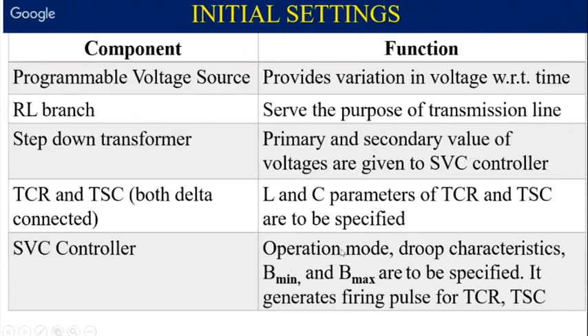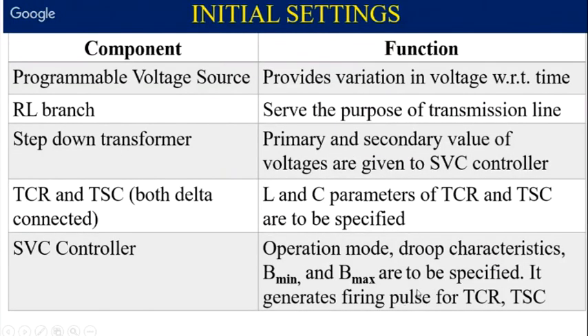And in the SVC controller, you should mention the droop characteristics of the SVC. Here you should mention the minimum and maximum susceptance that the SVC can provide. It is not a generator, this is an SVC. It will produce voltage as per its capacity. If all the inductance and all the capacitance are taken in the circuit, its maximum and minimum susceptance, and accordingly the reactive power it can provide, should be mentioned, and it generates firing pulses for this.